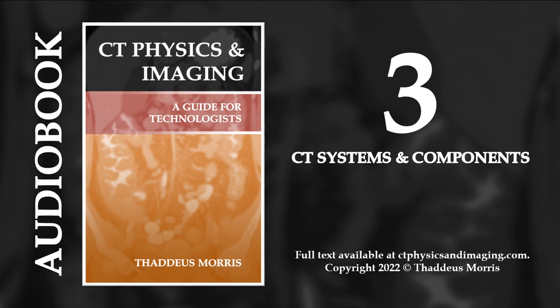This chapter discusses the physical systems of the CT scanner and the components that make image production possible. A CT scanner usually includes three connected systems: the scanner gantry and patient table, the data acquisition system (called the DAS), and the operator's console. Each of these systems supports different elements of the image production process. Figure 3.1 — a Canon Aquilion Large-Bore CT Scanner — demonstrates these three interconnected systems: the gantry and patient table, the operator's console (computer monitor and keyboard), and the data acquisition system (below the monitor).